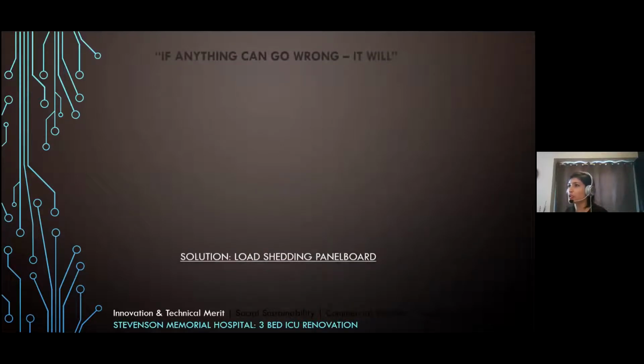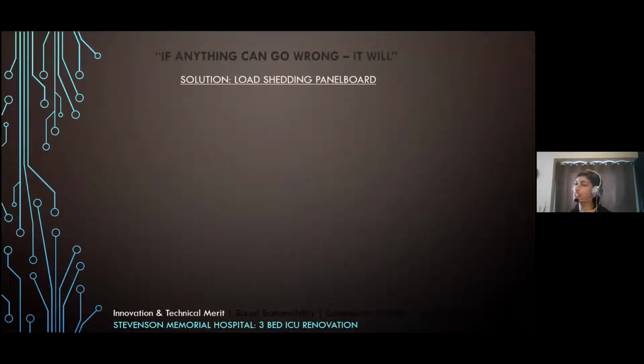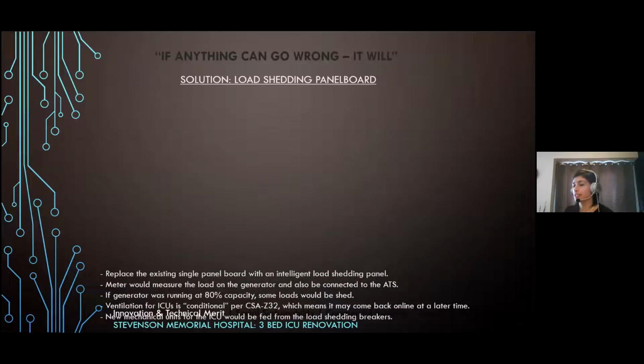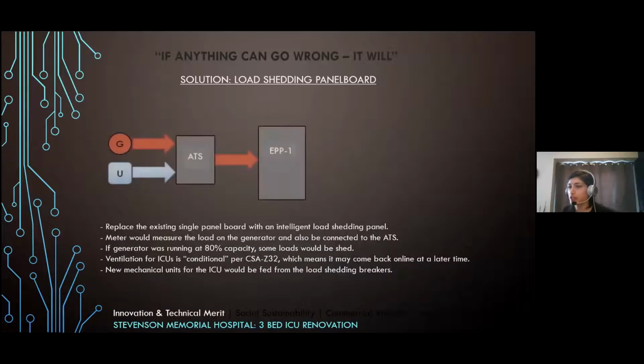Okay, so Murphy's Law top of mind. Our solution to solving our generator capacity problem was a load shedding panel. Here is a very basic version of our single line diagram. On the left, U represents utility power, G represents generator power. When utility power fails, the generator kicks in via the transfer switch, which feeds the panel.